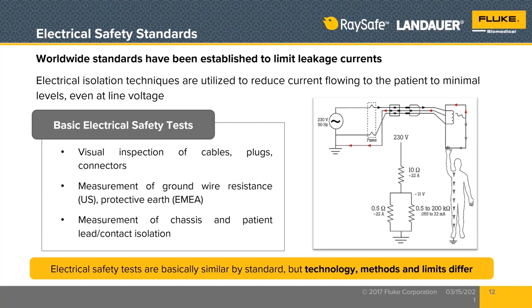testing. The 62353 is the electrical safety standard that applies to doing electrical safety testing once the medical device has reached the hospital or medical facility and will be put into their inventory. So prior to that, in the manufacturer, for design validation or for final assembly testing on the factory floor before the medical device is shipped to the hospital, IEC 60601-1 is the more appropriate standard for them to use.